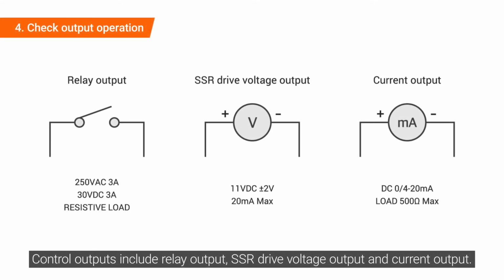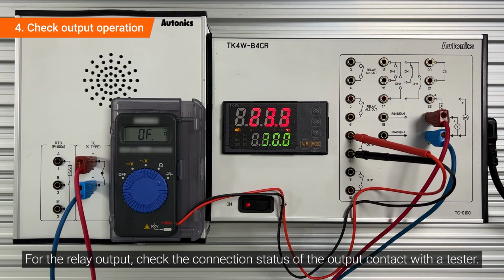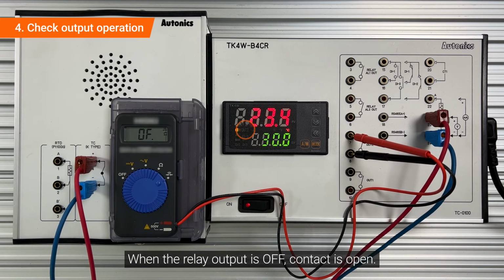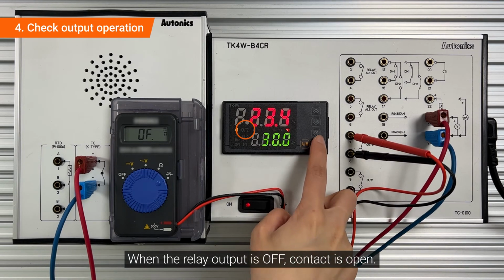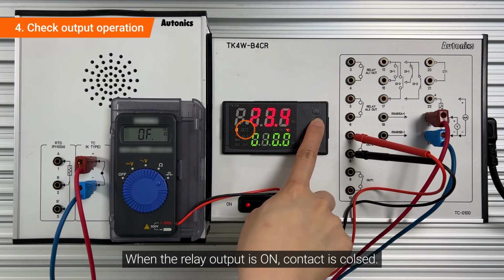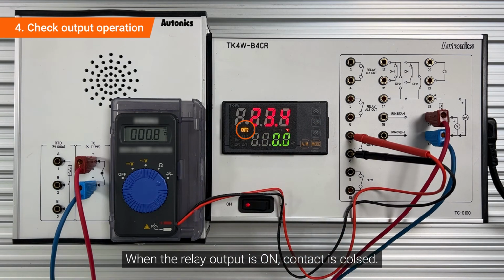Control outputs include relay output, SSR drive voltage output, and current output. For the relay output, check the connection status of the output contact with the tester. When the relay output is off, contact is open. When the relay output is on, contact is closed.